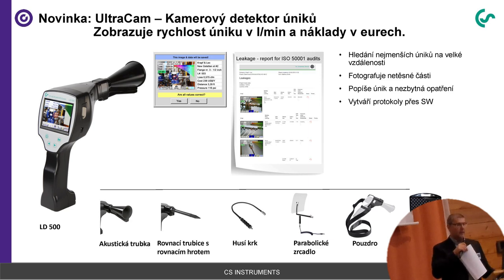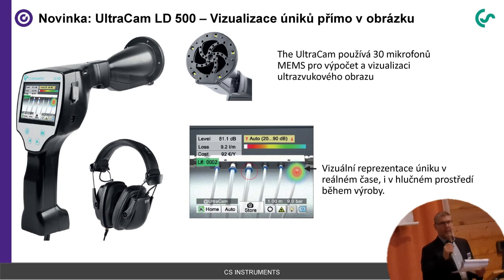And last but not least, we have also improved the leak detector. You can also watch the latest version over there. I took the LD500 UltraCam with me. It's the so-called UltraCam, which has 30 microphones. With the 30 microphones, we are able to create, let's say, a photo which shows the leakages graphically. So it works like a thermal imager. Probably all of you know the thermal imager, the infrared cameras. With this device, you can pinpoint the leak, and then you can see in the display that at this position there is the leak. It makes the work for the person who is looking for the leaks much easier, and it also helps you to save money and reduce your compressed air costs.